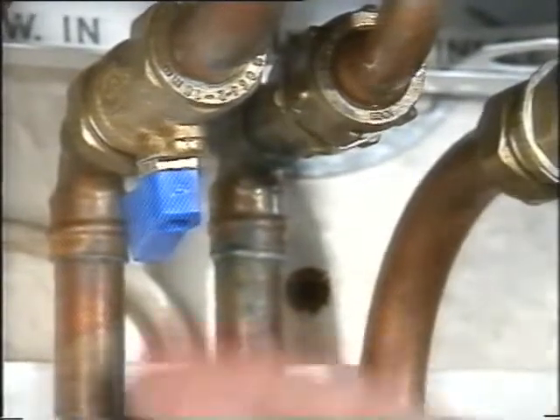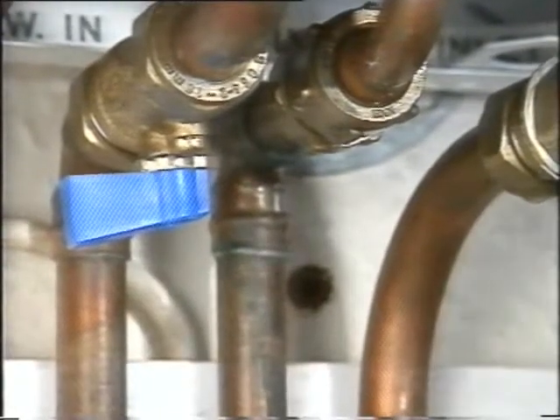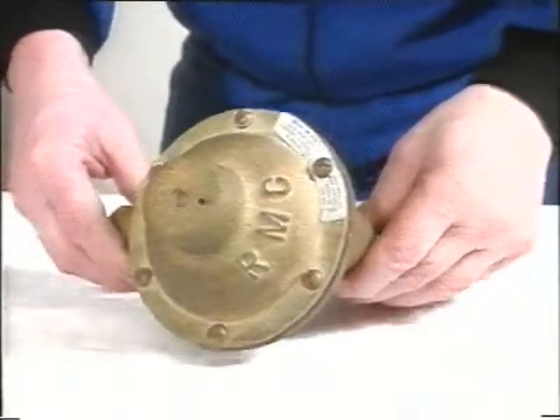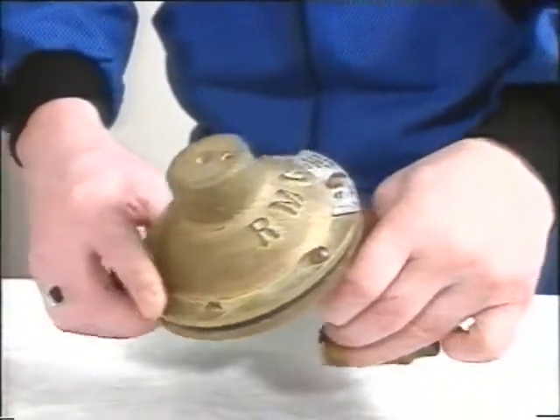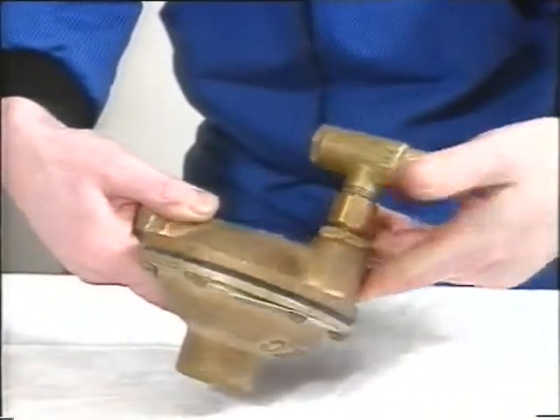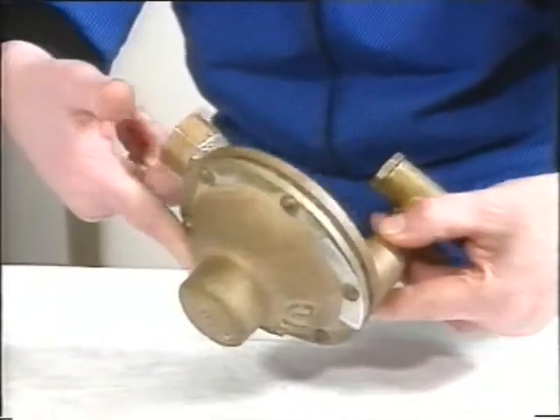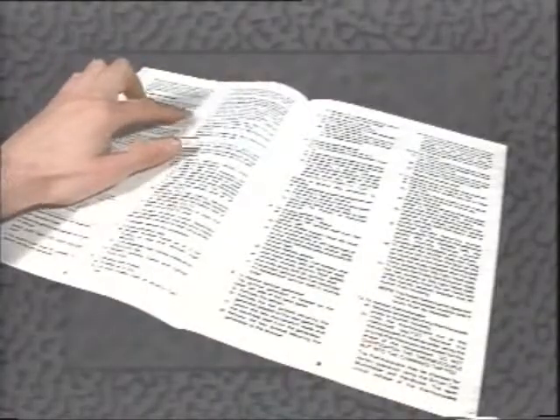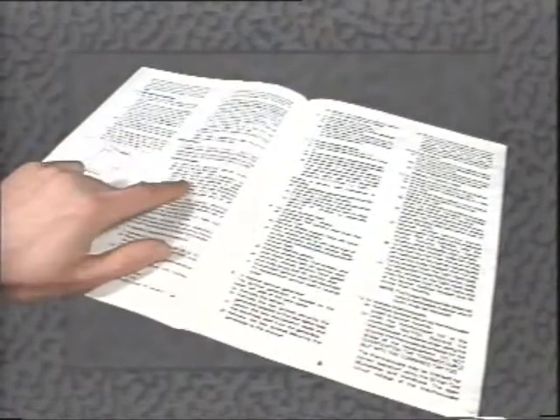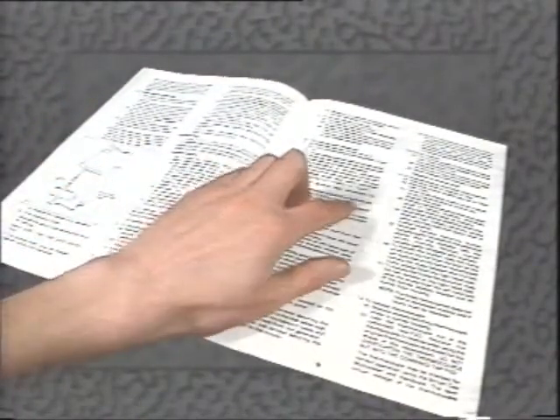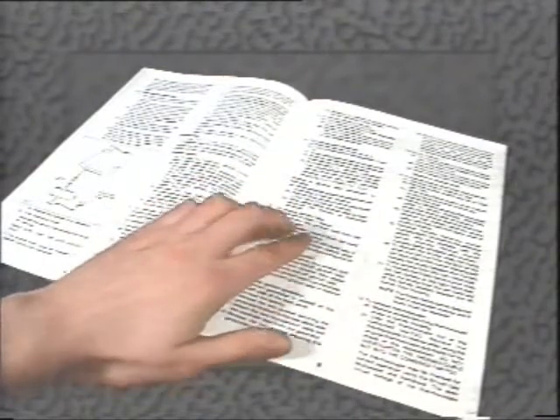A multi-point installation can either be connected directly to the water mains or to a feed system. A service valve should be fitted to the heater's cold water inlet so that the appliance can be isolated for maintenance. And if the water mains pressure is greater than that recommended by the manufacturer's instructions, it may also need a pressure-reducing valve. You'll need to check the manufacturer's notes as well if you're using a feed system, because the head of water is important. Remember too, always check the BS regulations.